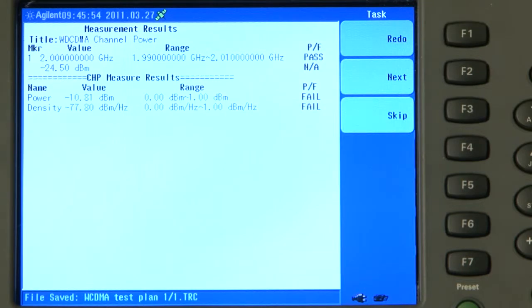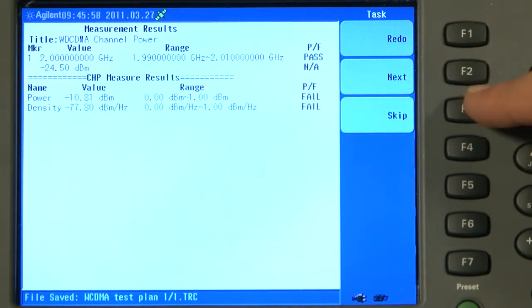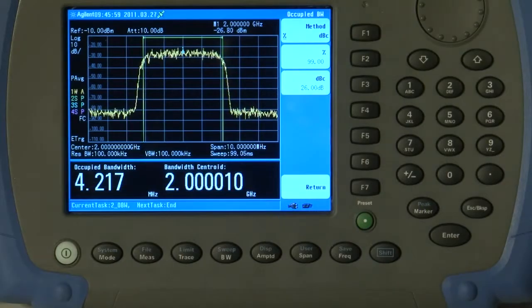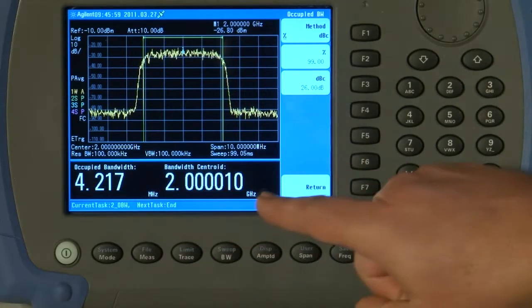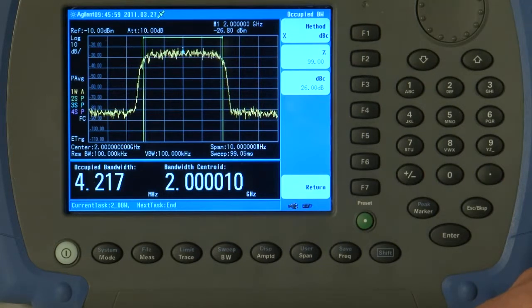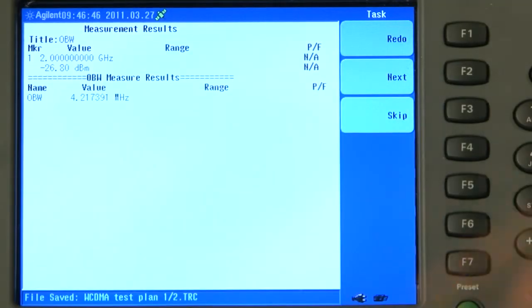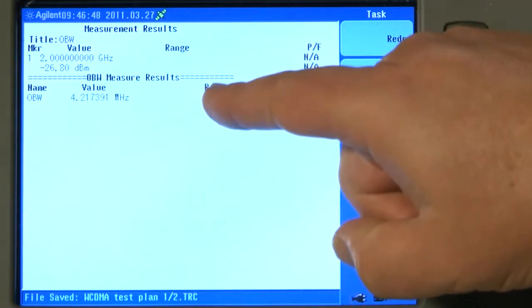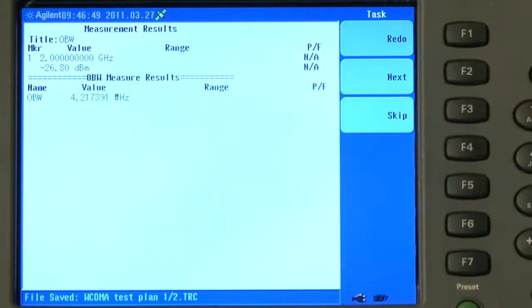The operator then is given the options of redo the measurement, move on to the next measurement, or skip. So we will press Next for the next measurement. And now it is measuring automatically the occupied bandwidth measurement we asked it to do in Step 2 of the Task Planner. Again, it is saving the JPEG images of the screen and it has added the measurement results now from the second task to our test report text file. We will press Next and Return.